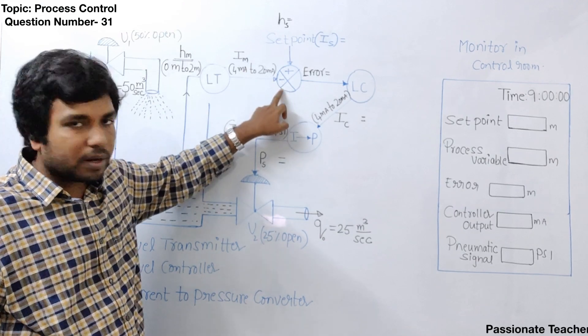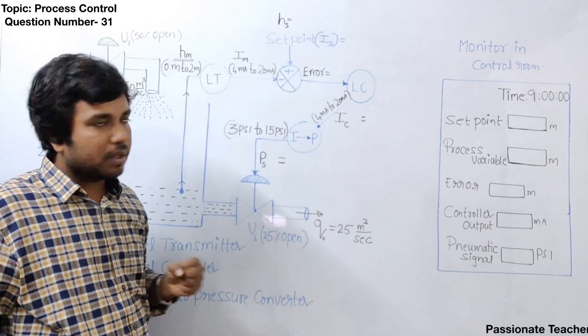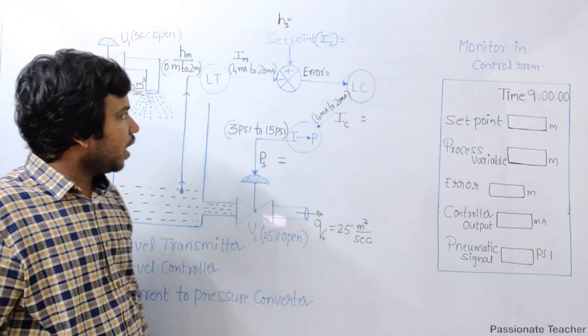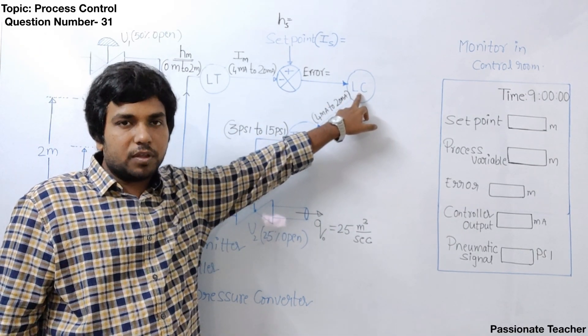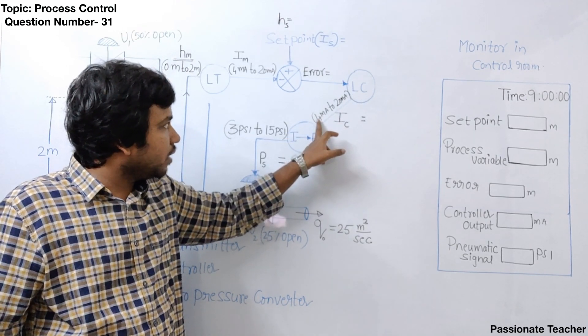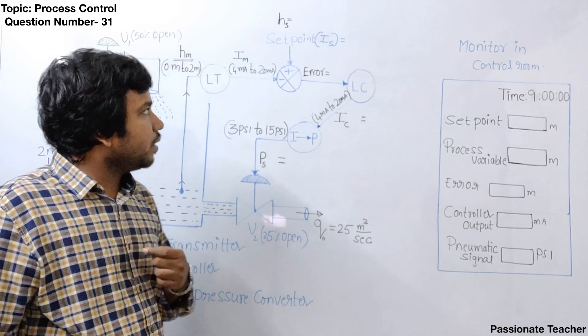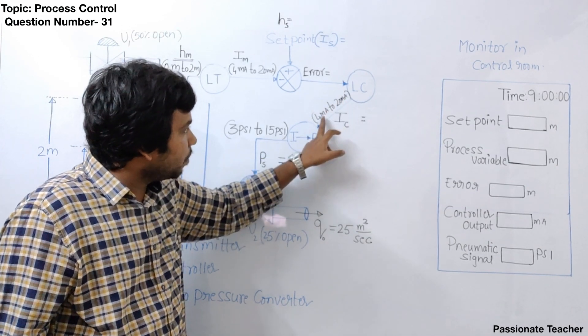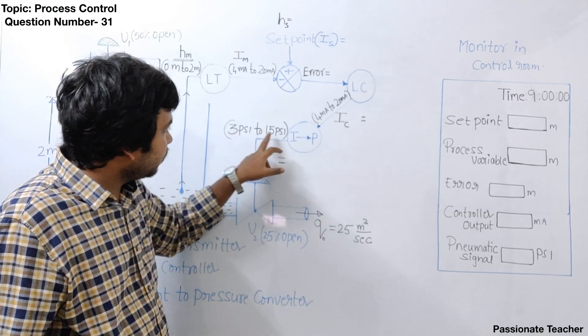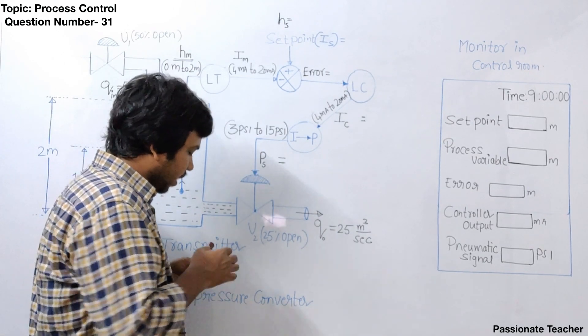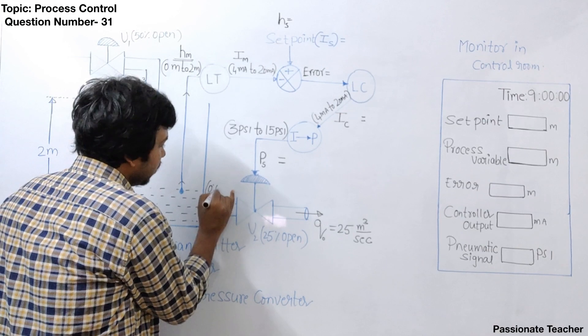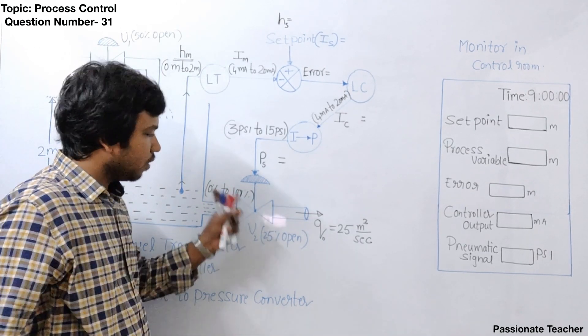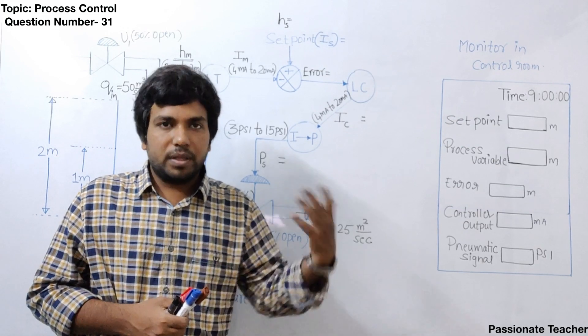Once the measured value is given to the error detector, it subtracts the measured value from the desired value, and the error signal goes to the controller. The electronic controller built with operational amplifiers generates a standard current in the range of 4 mA to 20 mA. This 4–20 mA current is then converted to a standard pressure of 3 psi to 15 psi, which corresponds to 0% to 100% valve opening. Zero percent open means the valve is fully closed; 100% open means the valve is fully open.